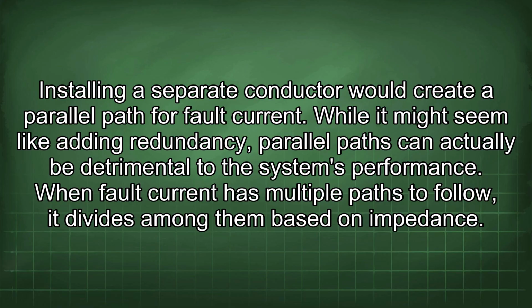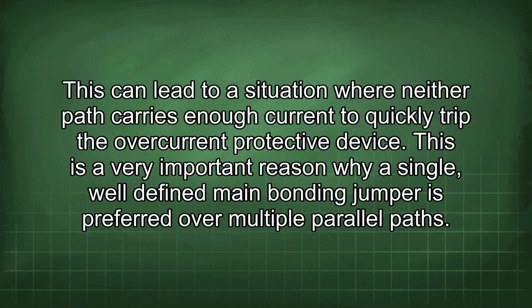When fault current has multiple paths to follow, it divides among them based on impedance. This can lead to a situation where neither path carries enough current to quickly trip the overcurrent protective device. This is a very important reason why a single, well-defined main bonding jumper is preferred over multiple parallel paths.